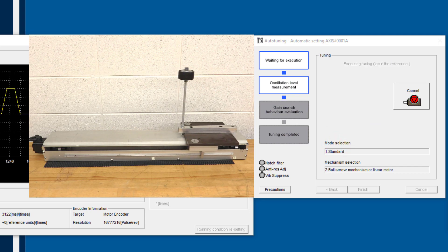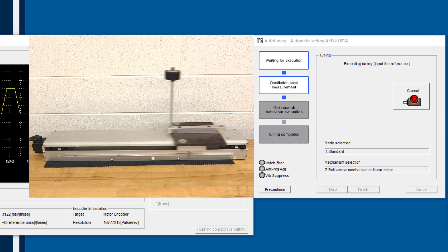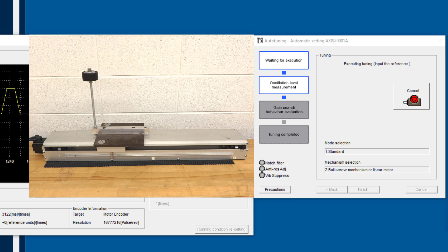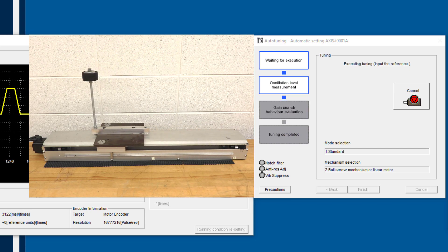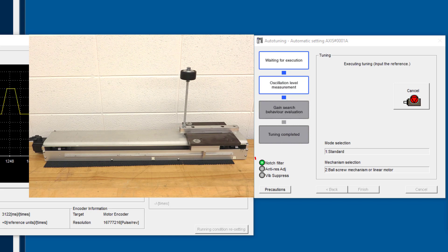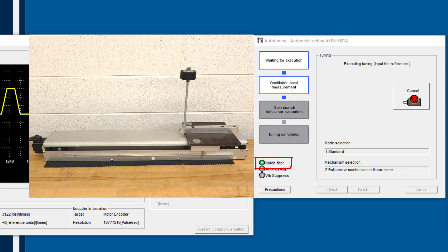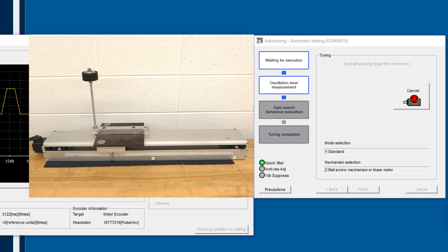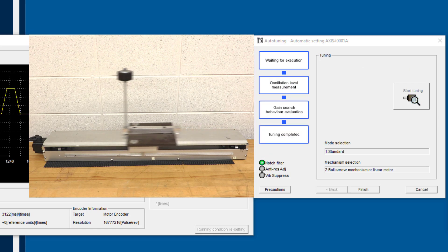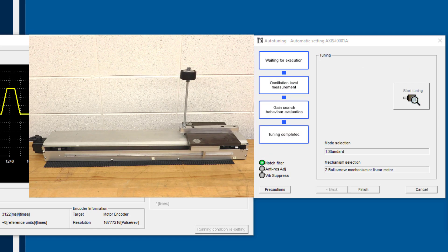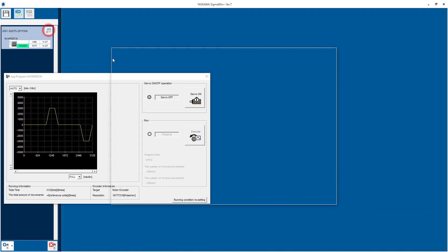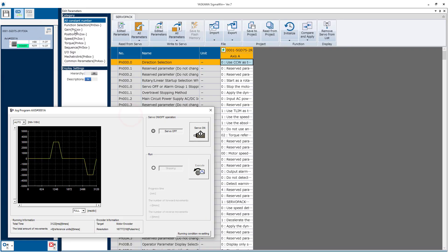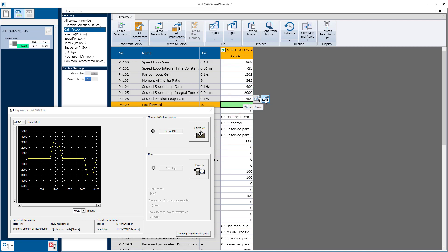It measures oscillation, searches for the best gains. Applies a notch filter. And tuning is completed. So finish, and finish, and I'll go back into the parameters to set PN109 back to 100%. Write to Servo.